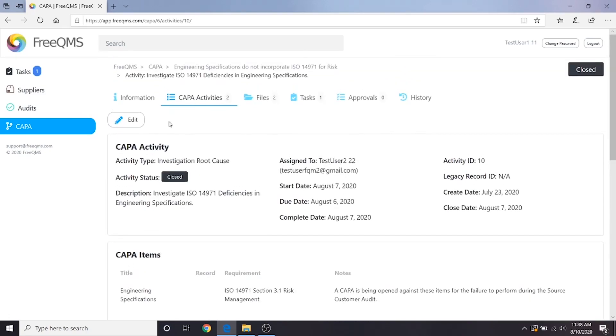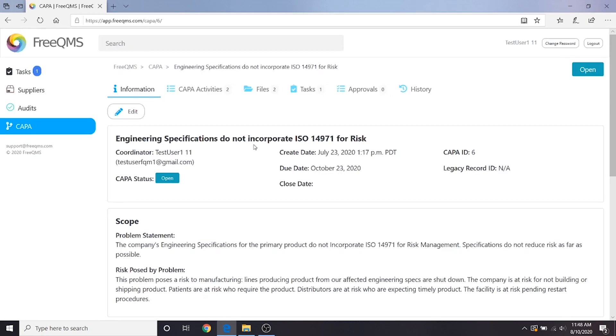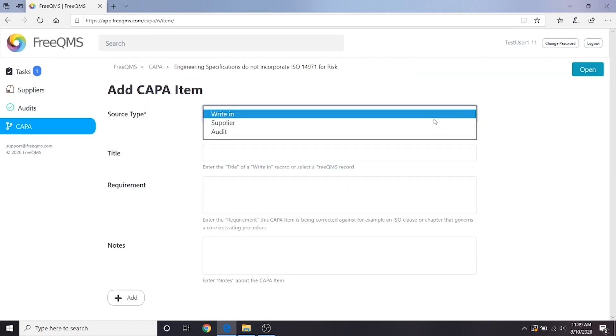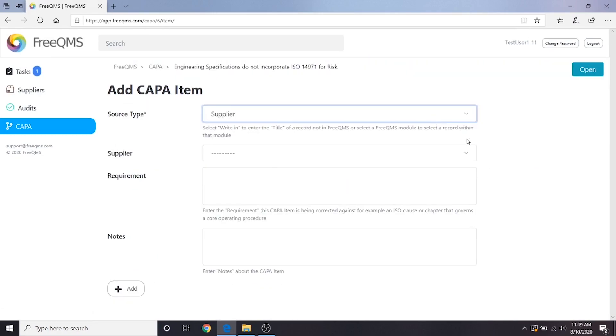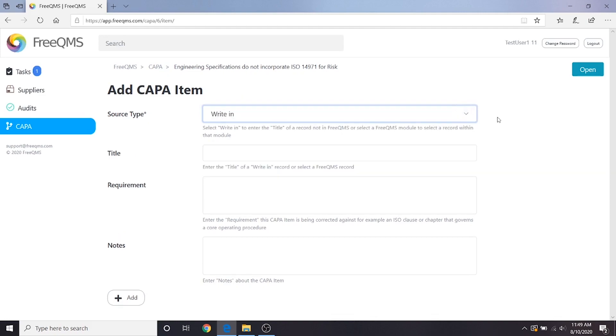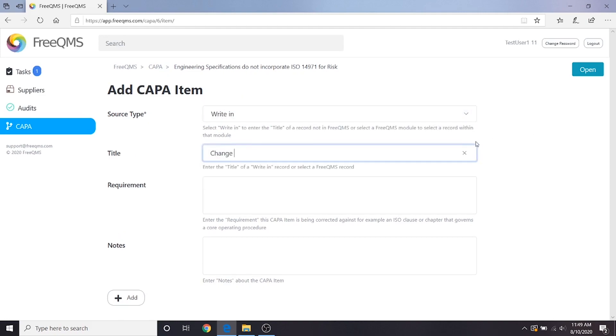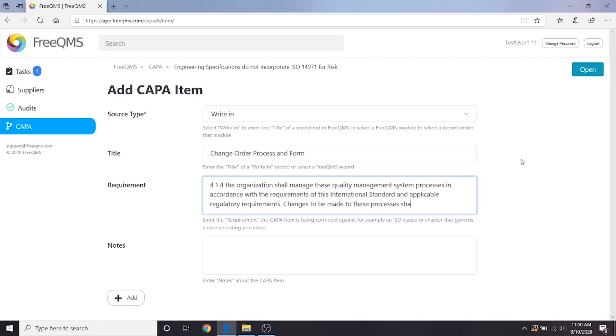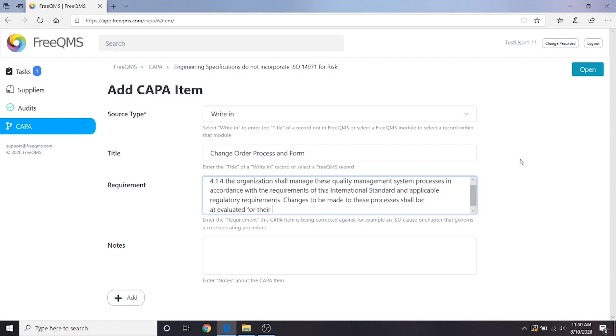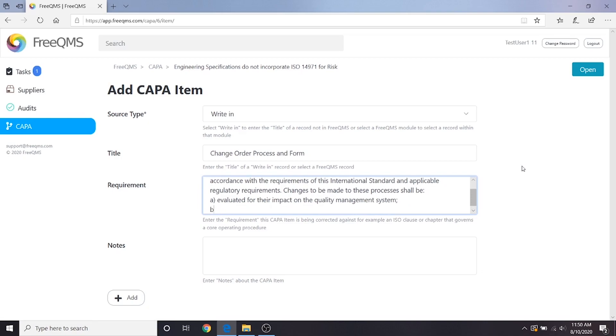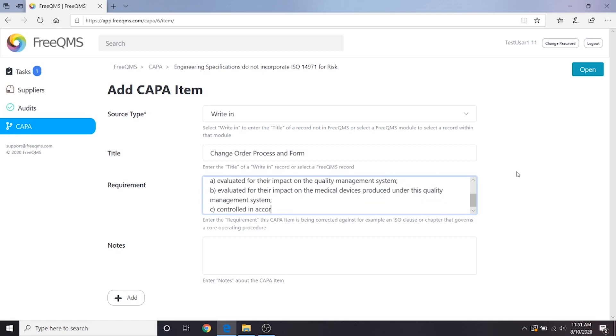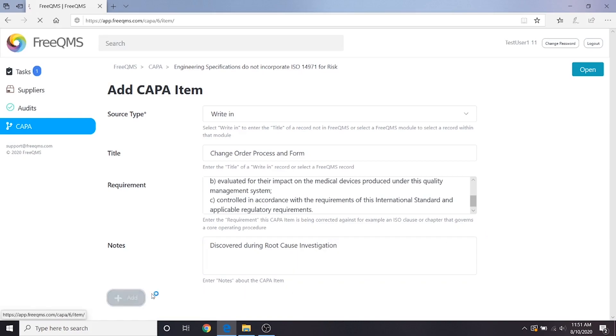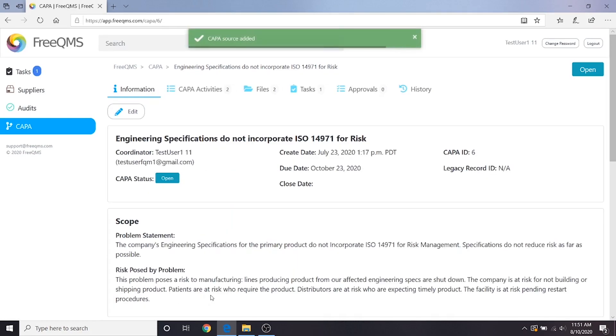Let's click the information tab. We're going to scroll down and click the add CAPA items button once again to add our change order process as something that needs a corrective action. We'll leave the top field as write-in. Our title will be change order process and form. Remember we're going to correct the underlying deficiency. For requirement, we will cite one of the core clauses of ISO 13485 2016. For notes, we'll put discovered during root cause investigation. Let's click the add button. Great, now we've added the CAPA items discovered during our containment and investigation root cause activities.